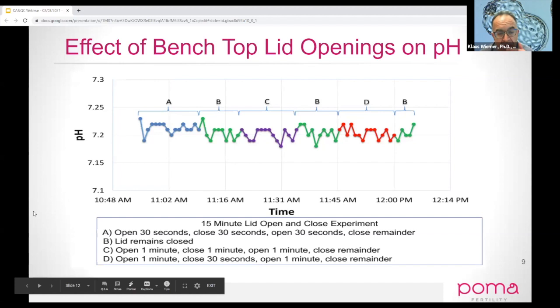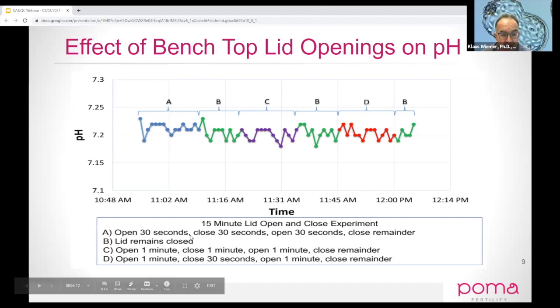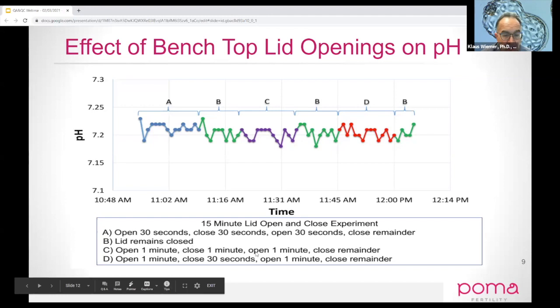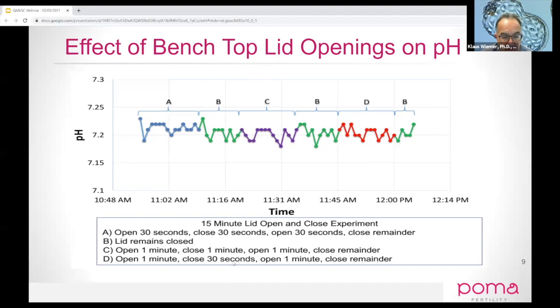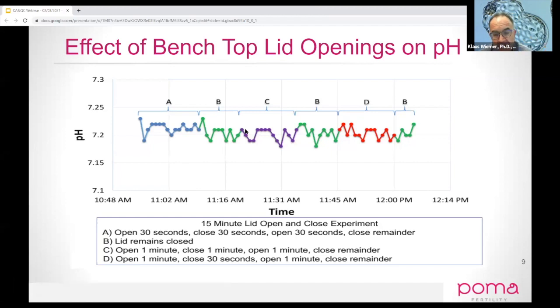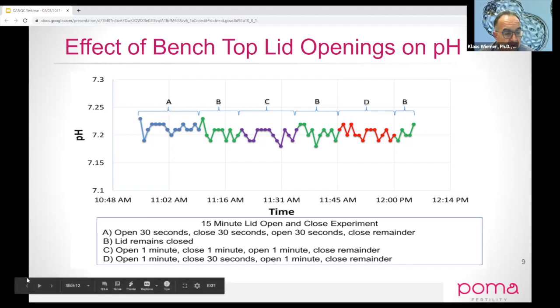Here's what happens with more of a benchtop opening scenario. We were opening dishes for 30 seconds and closing, repeatedly. Over the course of the experiment, our pH was going up and down but staying very relative to what would be physiologically okay for our embryos. Even leaving the dish open up to one minute and then closing for 30 seconds, the pH stayed in physiological range. These slides show that stabilization of our incubators is really dependent on the type of incubators and the type of sensors within them.